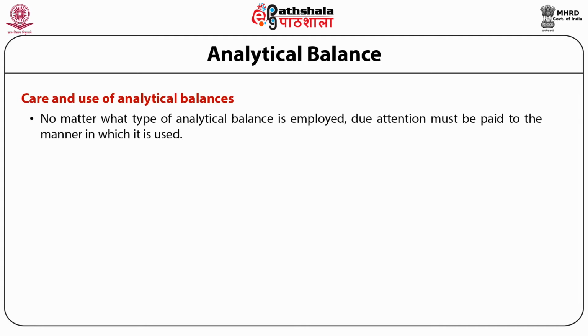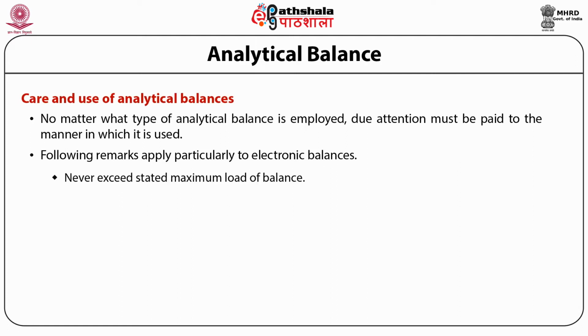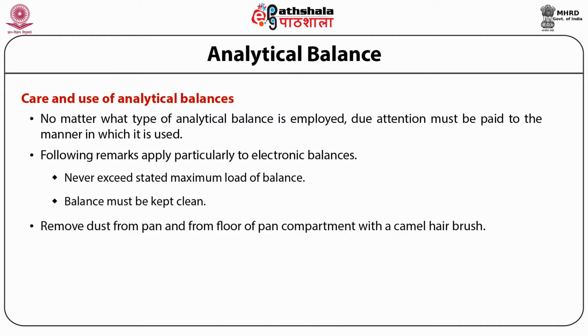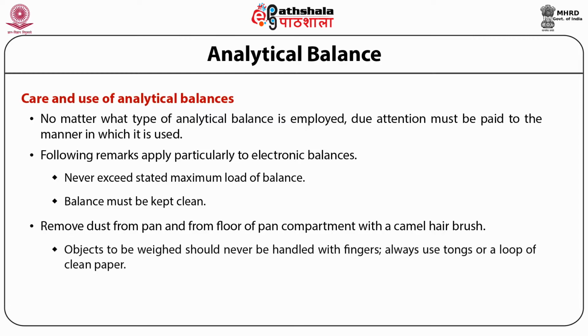Care and use of analytical balances. No matter what type of analytical balance is employed, may be classical balance or electronic balance, due attention must be paid to the manner in which it is to be used. The following remarks apply particularly to electronic balances. Never exceed the stated maximum load of the balance. The balance must be kept clean. Remove dust from the pan and from the floor of the pan compartment with a camel hair brush. Objects to be weighed should never be handled with the fingers. Always use tongs or a loop of clean paper.